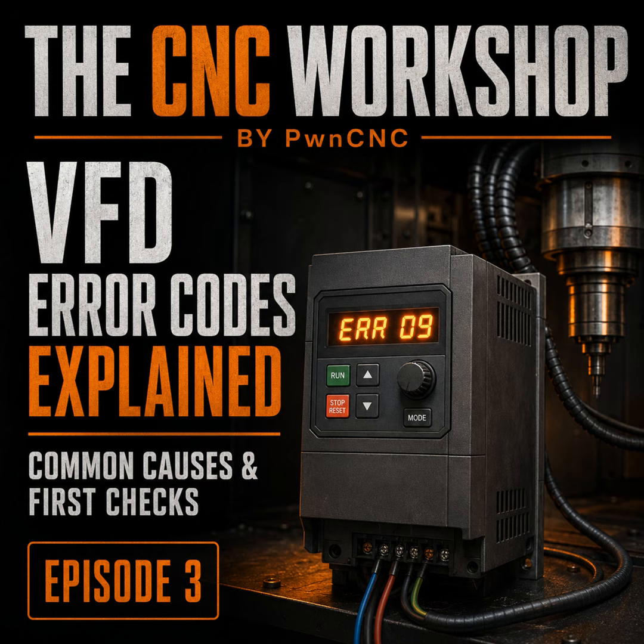Right. That is the big idea for this episode. A VFD error code is a starting point. You still need to consider what the machine was doing, when the fault occurred, whether the spindle was under load, whether an axis was moving, and what condition the cable and connectors are in. In other words, the machine says, something is wrong, and then leaves us to conduct the investigation. Pretty much. But the code narrows the investigation, and that can save a lot of time if we use it correctly.